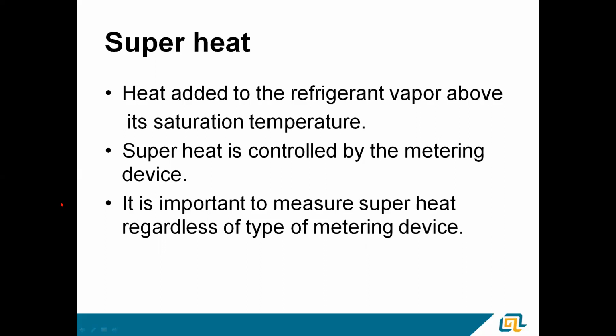It's very important to measure superheat regardless of your type of metering device. For many years, I've always heard that, well, you know, I got a TXV, so all I have to do is check my subcooling. Yes, that is correct. You charge by subcooling, but you check by measuring the superheat coming off of that valve. So if you're charging a system or doing any service to a system with a TXV, you've got to check your subcooling to make sure the charge is accurate, and then check your superheat to make sure the valve is performing well.